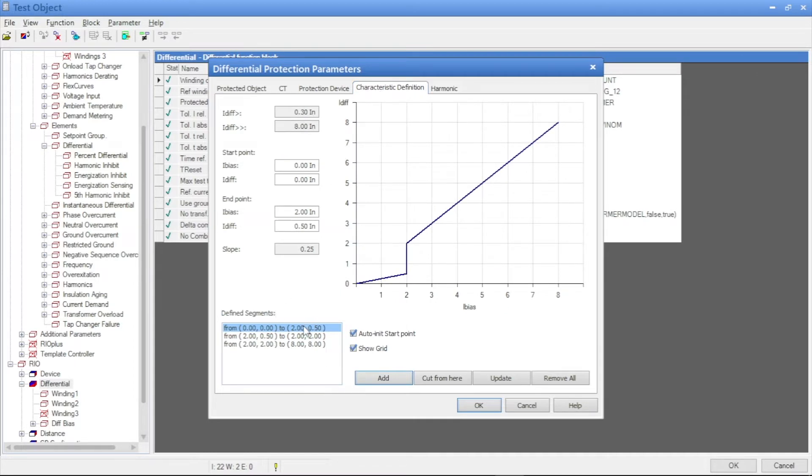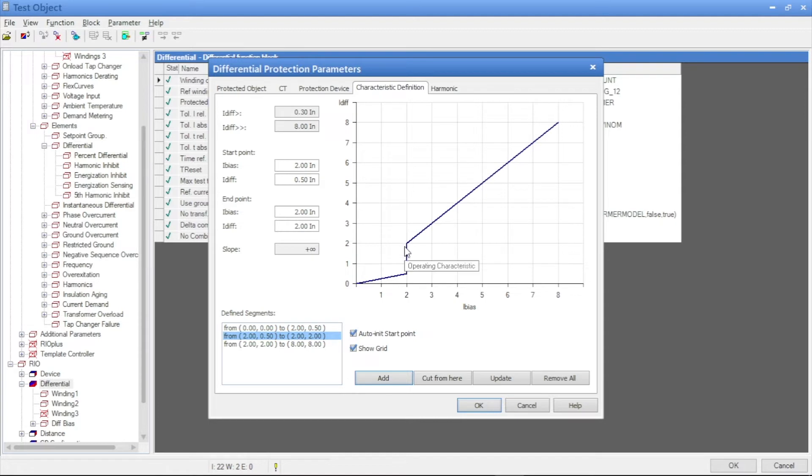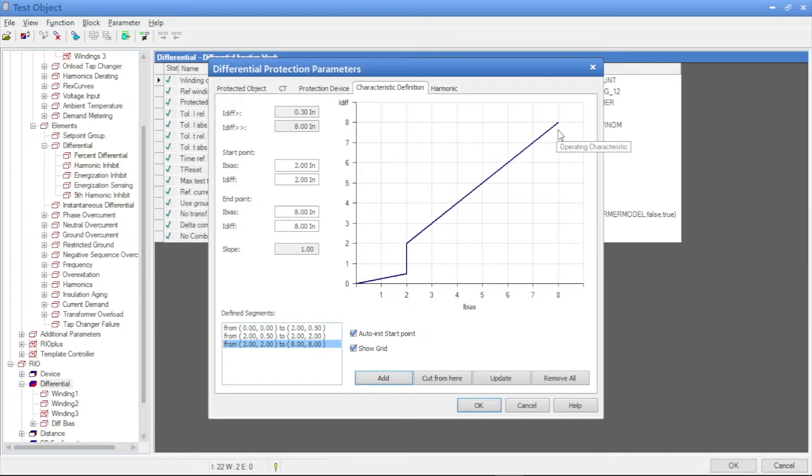And we have seen here the slope 1, 25% is the first one. And the middle one is the knee point for the CT saturation. And second one is the slope 2.